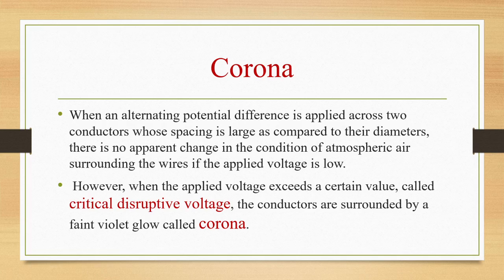As the corona phenomenon is initiated, a hissing noise is heard and ozone gas is formed, which can be detected by its characteristic odor. So how do we know whether corona has occurred or not? Whenever corona is occurring, we can hear a hissing noise, ozone gas is formed, and the color also changes: a faint violet glow comes into the picture. At that time we can say that the corona phenomenon has initiated.